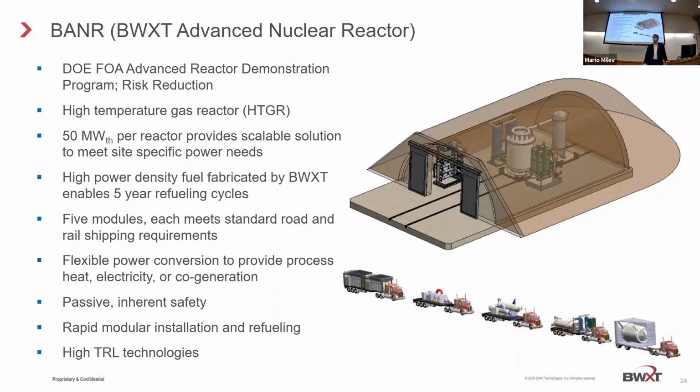Yeah, this is just an aside. An interesting feature of the TRISO type designs is that if you have a point failure in the core, let's say something happens and you lose a whole TRISO compact, it's a really different accident scenario than if you even just poke a hole in an LWR fuel rod. If you poke a hole in an LWR fuel rod, you lose the entire fission gas that's in the rod, right? But if you have a point failure in these, it's only the fission product inventory for the failure location.